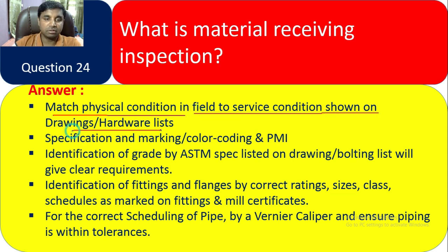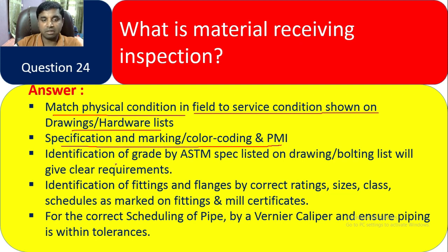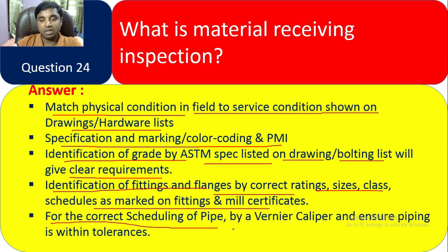Question 24: What is material receiving inspection? We match the physical condition in the field to the service condition shown on the drawings. We check specification and marking, color coding, and PMI. We verify identification of grade by ASTM specification listed on the drawing, and the bolting list. We check identification of fittings and flanges by correct rating, size, and class in the mill certificate. We also verify correct scheduling of pipe using a Vernier caliper and ensure piping is within tolerance.